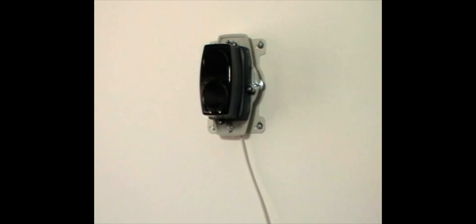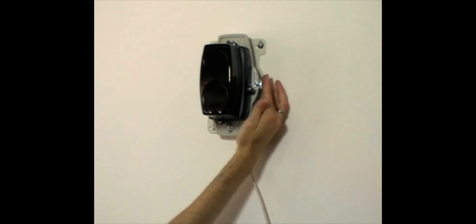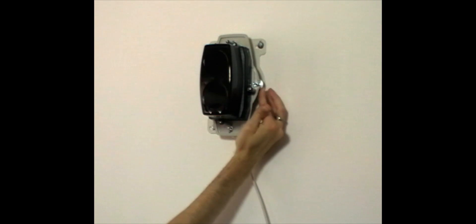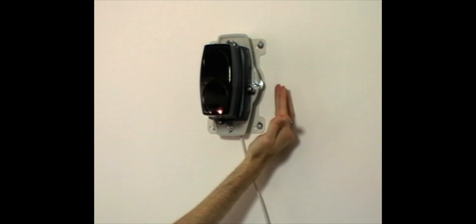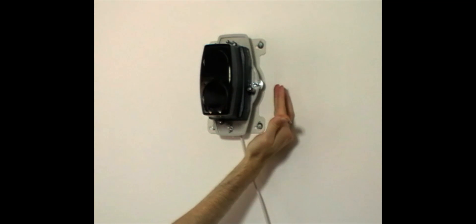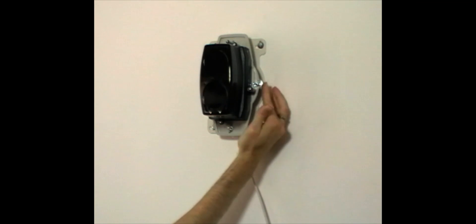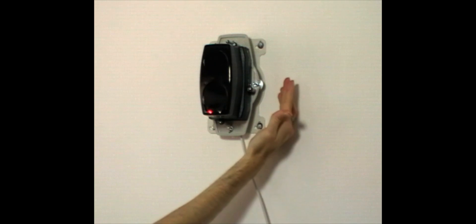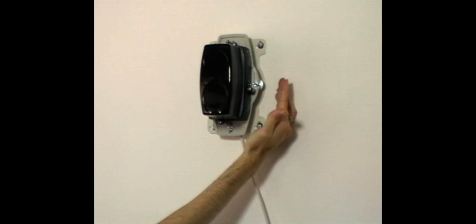Choose a thumb wheel. It doesn't matter which one you choose first. We are going to adjust both of them. Turn half a turn. If you get the amber LED, stop. You are going the wrong direction. Turn back a half turn and you get the red LED.